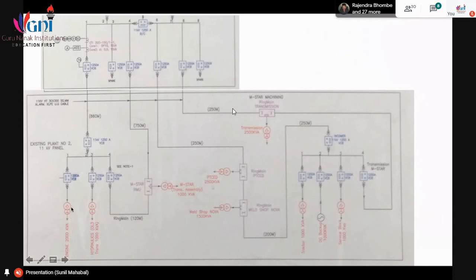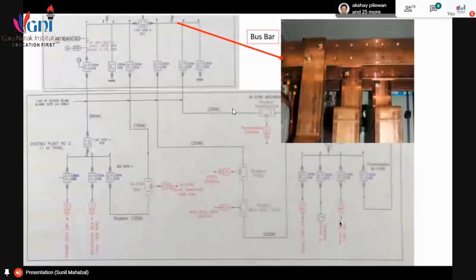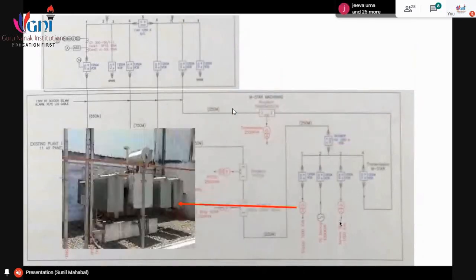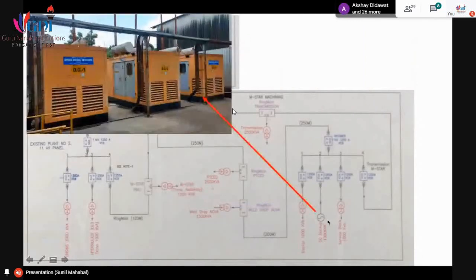Now this particular transformer, 11 kV to 440, delta star, is going to the engine department, 2000 kVA. Then hydraulic, this is another department. There also it is delta star and 1000 kVA. Then this is for transmission. Then this is for weld shop. This is for PTCD. These are the different departments which are fed through 11 kV. And you can also see the bus bar through which the distribution happens. And you can also see the picture of a transformer, 11 kV to 440. And here you can also see the generators, which are given as standby. Whenever MSCB supply is not there, these generators will work as standby supply.